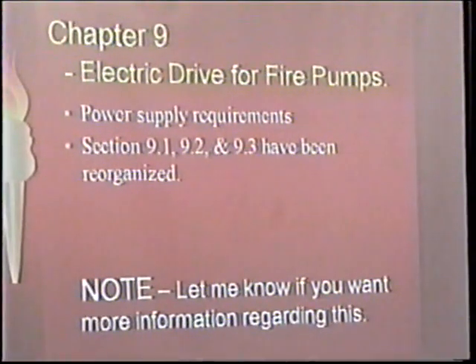And same for alarm conduits. Alarm conduits are not mandated to be anything but standard pipe and wire. Well, I'm saying that conduit from my controller entrance out to the first box needs to be watertight, and it needs to be sealed at that first junction box, so that water can't get into that junction box and run down the pipe into that controller. These are little things, but the only way that I have to make sure that they happen is to hold that warranty as the issue. So we'll start seeing that.